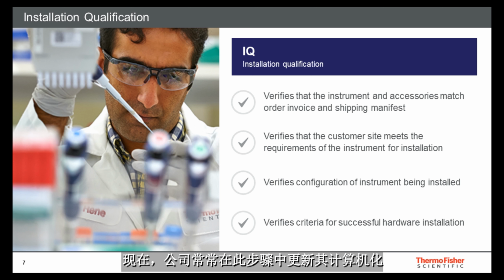Now, it's also common for companies to include updating their computerized maintenance management system, or CMMS, at this step. This ensures that the new asset is in the system and all maintenance activities are being tracked and documented. This is also the place that future scheduled PMs can be pre-scheduled so that the instrument will be maintained in a qualified state.